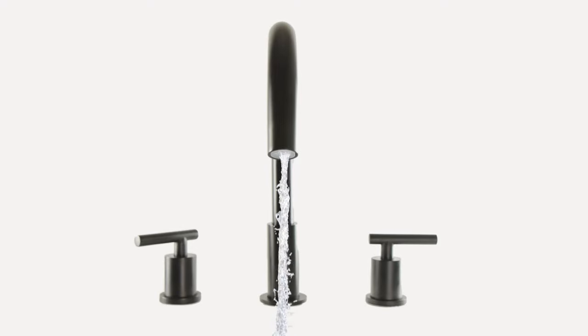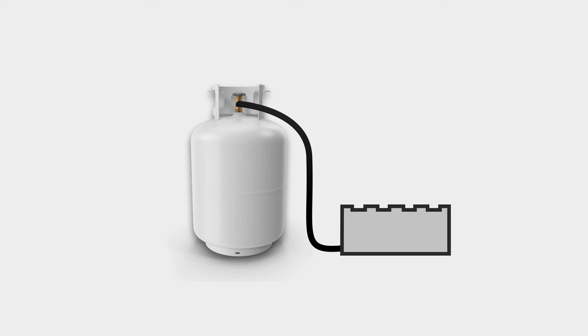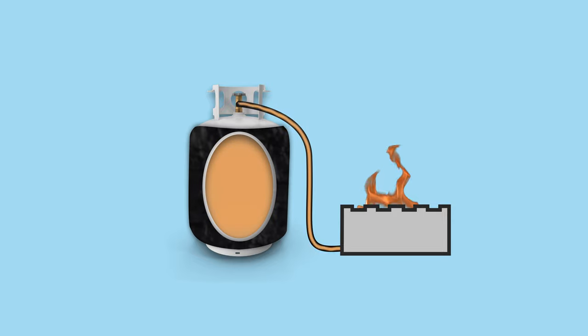The final factor to consider is the flow of propane gas coming to the water heater. In winter, propane can freeze up in your propane bottles, which in turn reduces the gas flow to the water heater. To help with this issue, we recommend you install a tank blanket around your propane bottles. If you are in an extremely cold area, you may want to consider a heated blanket.